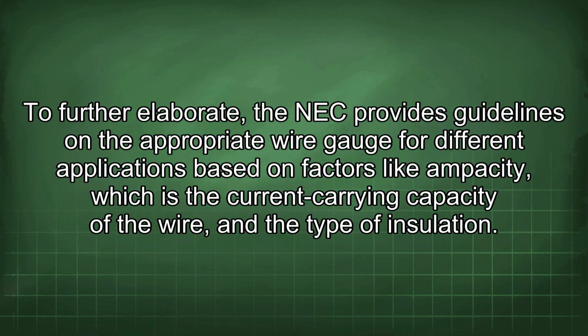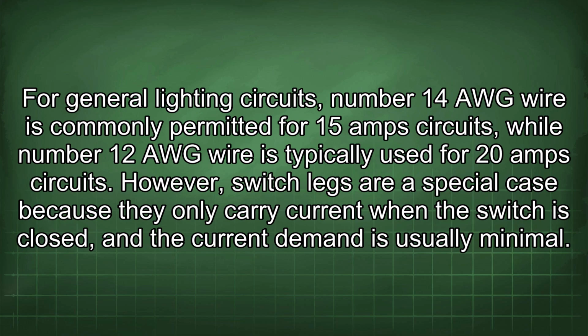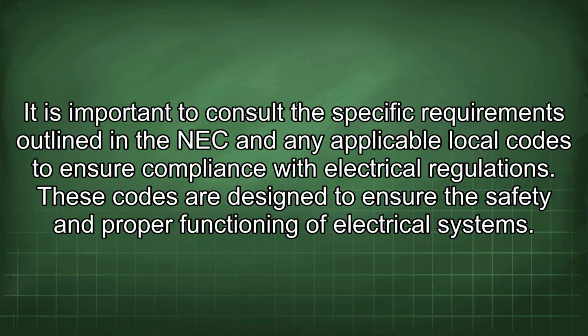To further elaborate, the NEC provides guidelines on the appropriate wire gauge for different applications based on factors like ampacity, which is the current carrying capacity of the wire, and the type of insulation. For general lighting circuits, number 14 AWG wire is commonly permitted for 15 amp circuits, while number 12 AWG wire is typically used for 20 amp circuits. However, switch legs are a special case because they only carry current when the switch is closed, and the current demand is usually minimal. It is important to consult the specific requirements outlined in the NEC and any applicable local codes to ensure compliance with the electrical regulations. These codes are designed to ensure the safety and proper functioning of electrical systems.